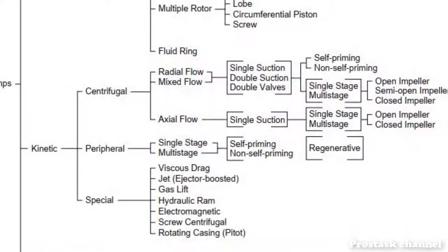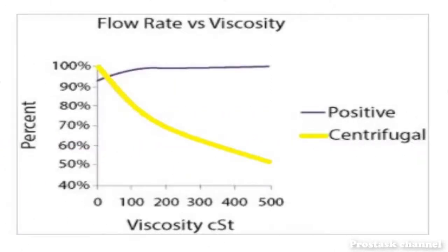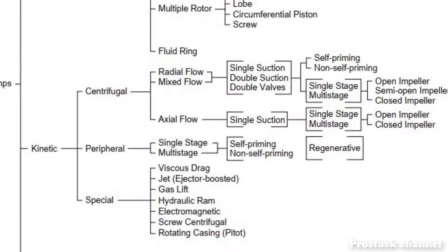The characteristics of kinetic pumps include discharge pressure that is free of pulsation and efficient performance over a range of heads and capacities. However, discharge volume is varied and very sensitive when system pressure changes, and discharge pressure is a function of fluid density. Lastly, kinetic pumps are more economical than positive displacement pumps.